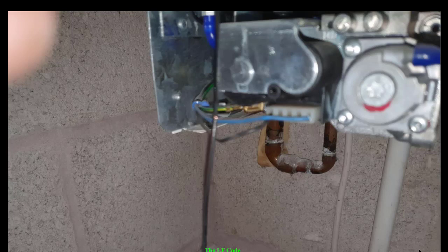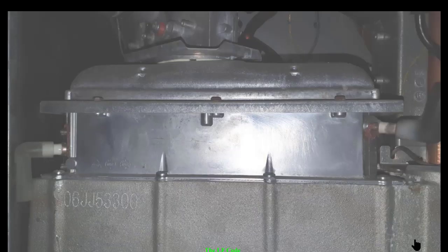If that's open and you've got standing pressure, then the next thing you can do is run the boiler and see if that standing pressure drops. Now if it doesn't drop when it goes to ignition, then you've definitely got a gas valve problem, it's not opening. So that's the area you can look at regarding the gas valve.